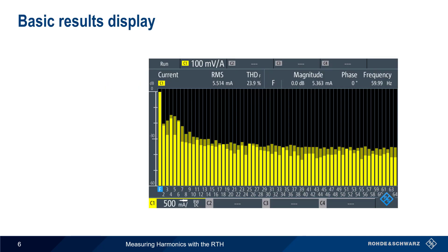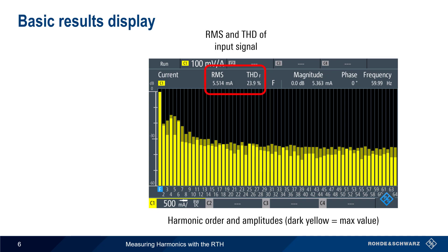Let's start by looking at the basic results display. The amplitude of each harmonic is represented by a bar with a number underneath showing the order of the harmonic. Yellow indicates the present measured value, and dark yellow indicates the max values seen since the start of the run or since results were last cleared. RMS and THD are the root mean squared value and the total harmonic distortion of the input signal. By default, the magnitude, phase, and frequency of the fundamental are also displayed.